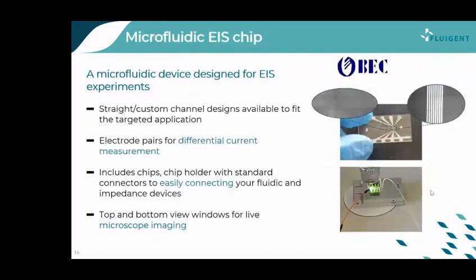Thank you, Meng. To perform microfluidic EIS, of course, you also need a microfluidic chip. BEC developed the EIS chip used here. The channel design can be customized according to your needs. The chip consists of a straight channel with custom dimensions, with two sets of double electrodes for EIS measurements. It is also possible to have two channels that meet the main one, for instance to hydrodynamically focus the cells or particles, or even for droplet generation. The microfluidic chip comes with a package including an EIS chip holder, 3D connection kit, and test signal connection kit. It is specially designed to avoid complicated fluidic and electrical connections to the chip.